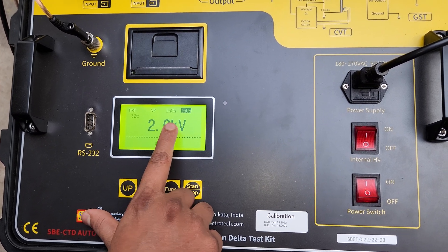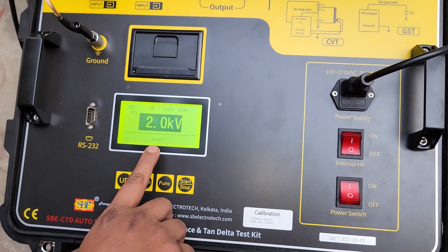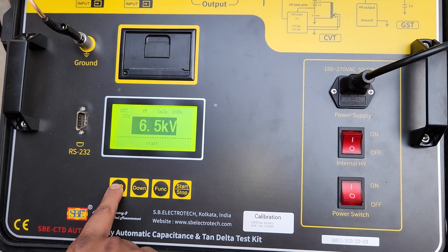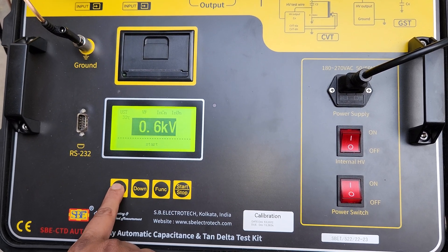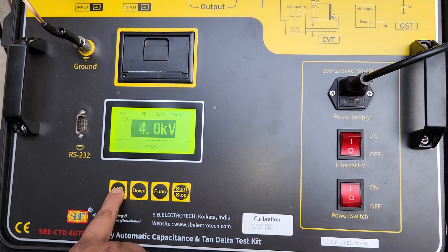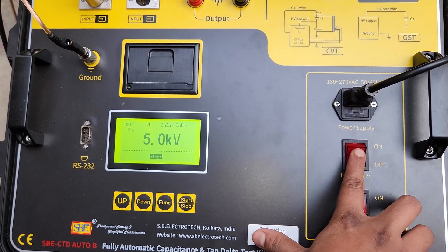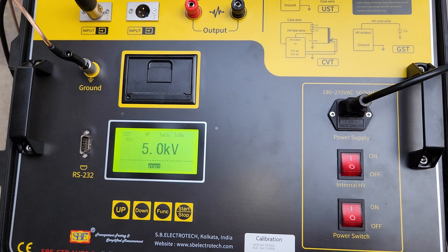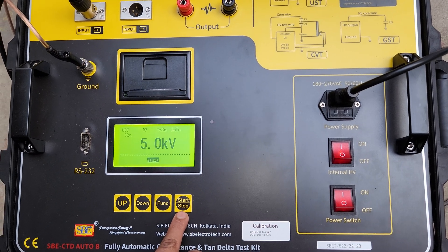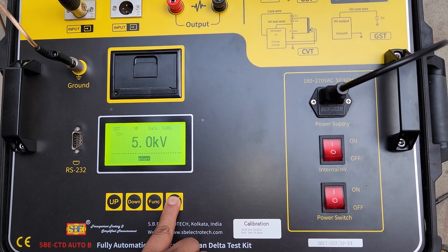These two will be INCN and INUN because here is the internal HV. We will test at 5 kV, but we can test from 0.5 kV to 12 kV maximum. For testing, we have to switch on the internal HV and wait for 3 seconds. After 3 seconds, we will click this start-stop push button for 3 seconds again and release it.